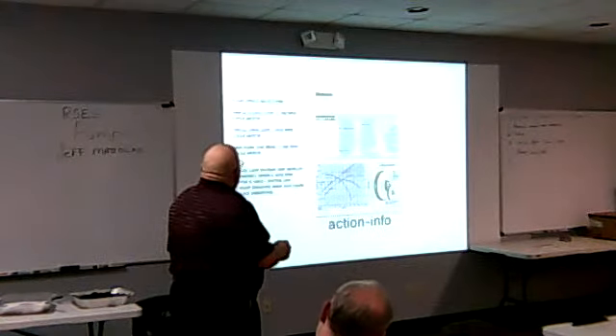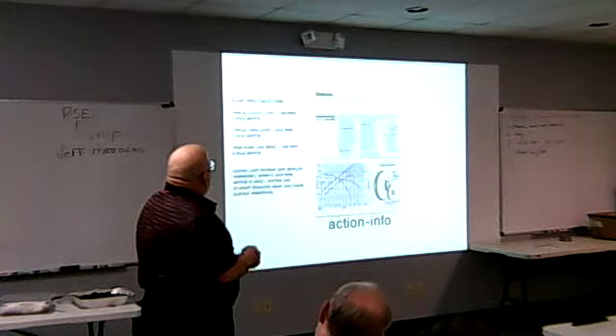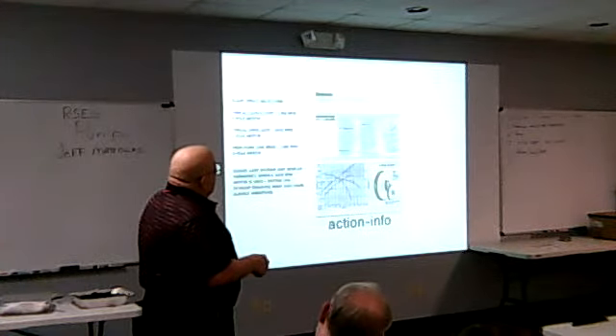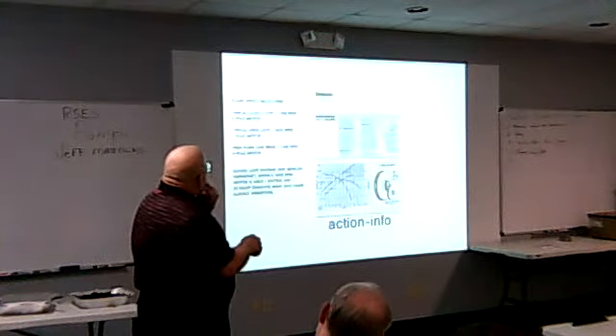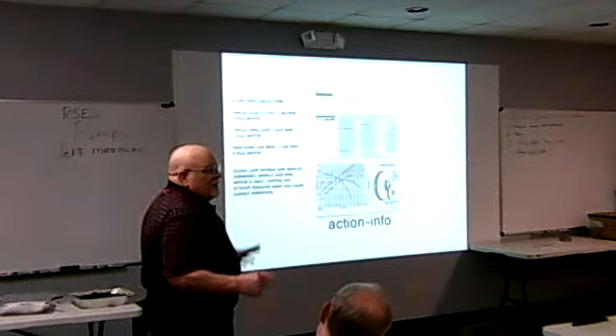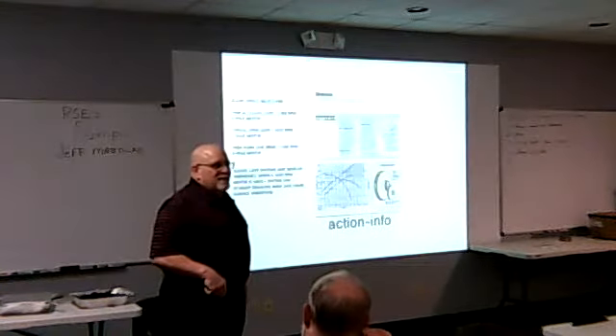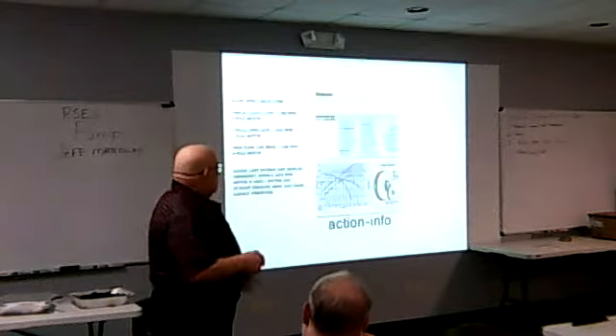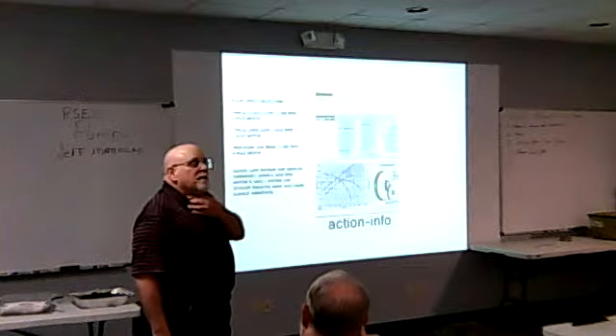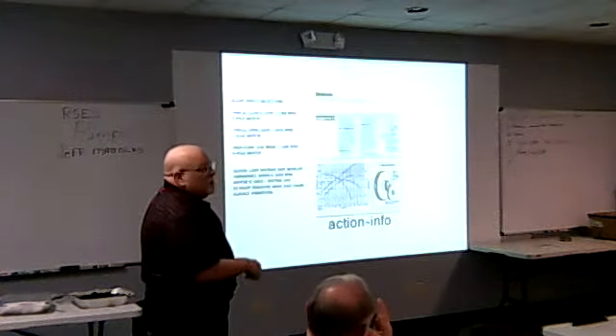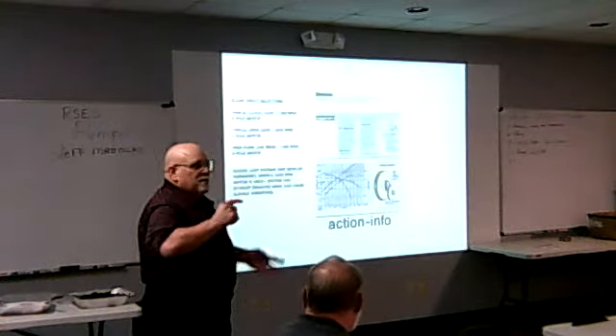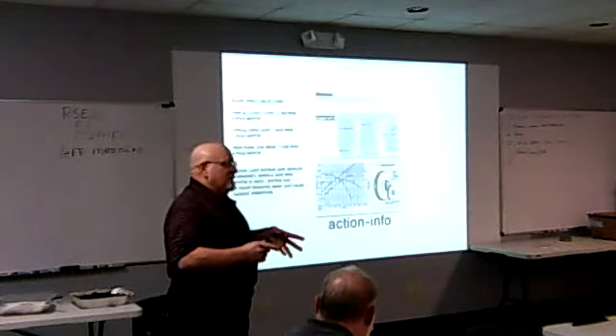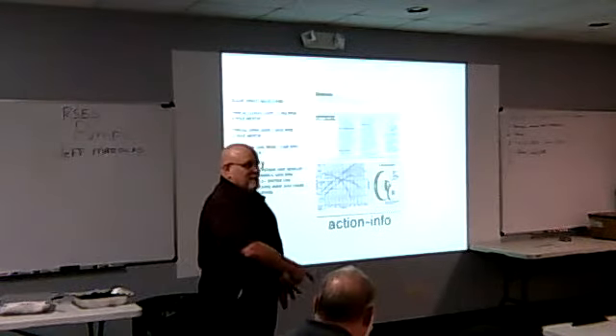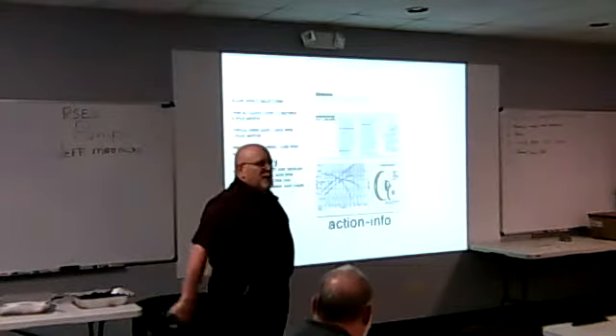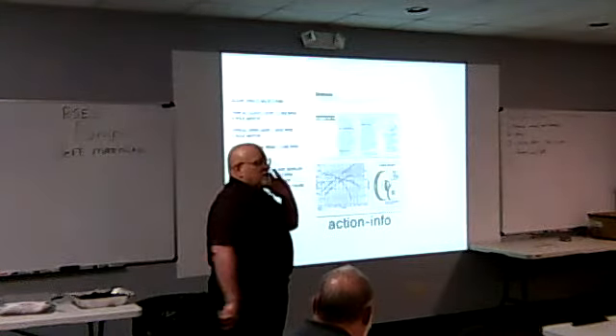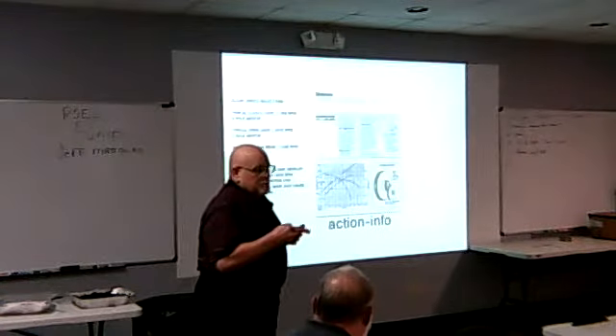Okay, this is another thing. Remember we talked about the affinity laws? Here's a 4-pole motor, 1760, 1160. This is a 1750 impeller, like this one is. The equivalent impeller for a 3500 would be this size. They get much smaller. They're spinning faster. Okay, with that RPM you're getting your energy from the speed, and the impeller weighs less. Is noise the only detriment? Pretty much. But the problem is, the higher I go in speed, it affects my NPSH. It needs more NPSH at 3600; it drops at 1760. And on a lot of big towers that I do have to lift, I'll lift at 1160 because of the NPSH requirements. So they're not churning as much, and you get a lot better net positive suction performance. And those are all calculated on your curves. Any questions?